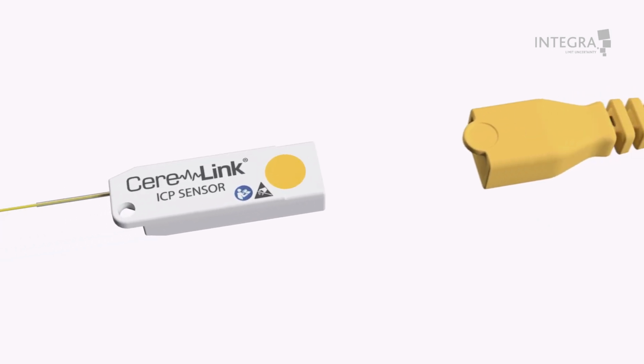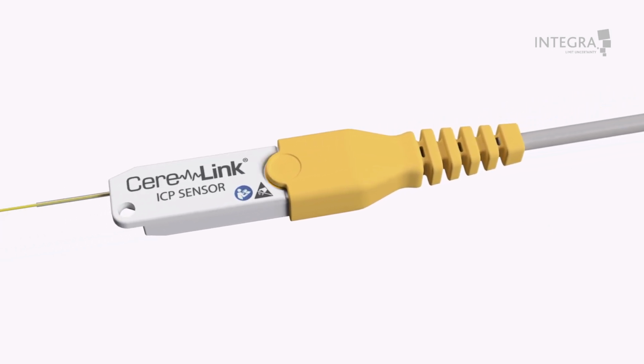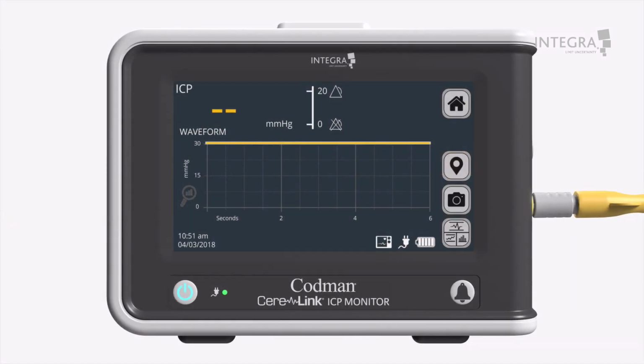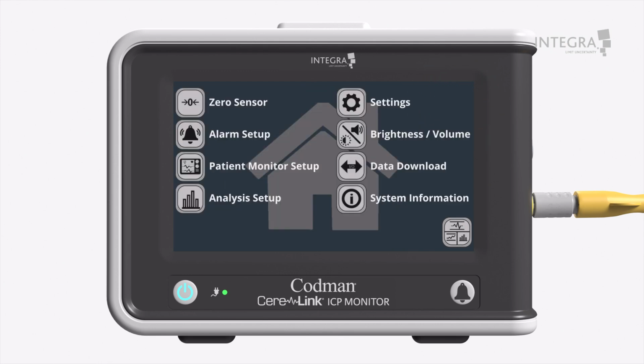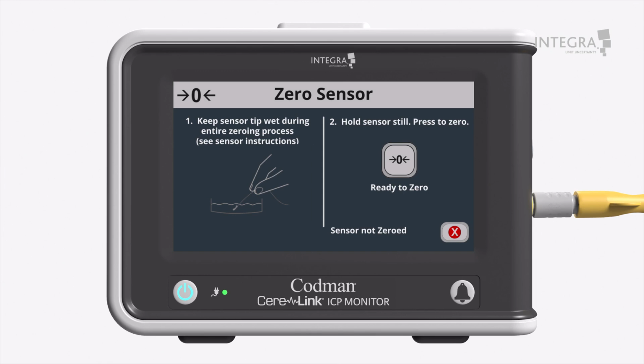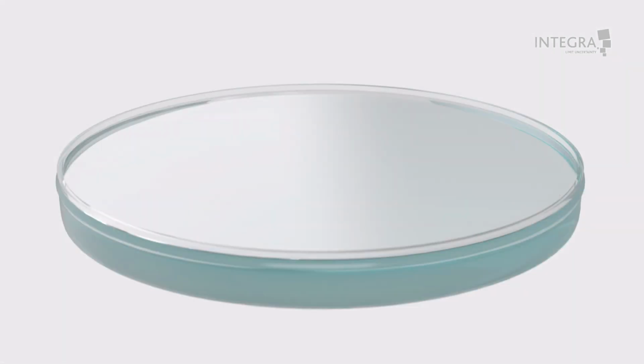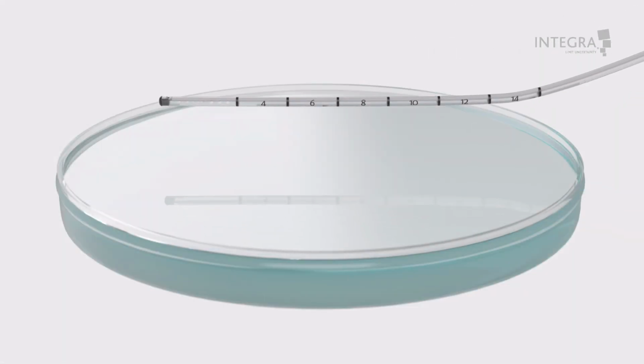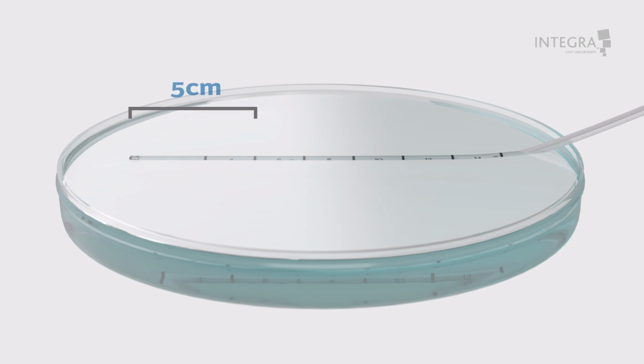Whilst maintaining a sterile technique, connect the ICP sensor to the ICP extension cable. Once the sensor is connected, the CereLink monitor will play a sound and will also display a 0 symbol. Press the Home tab on the CereLink monitor. Then press the 0 sensor tab. Using sterile technique, lay at least a 5 cm section of the sensor horizontally just under the surface of the sterile water or sterile saline.